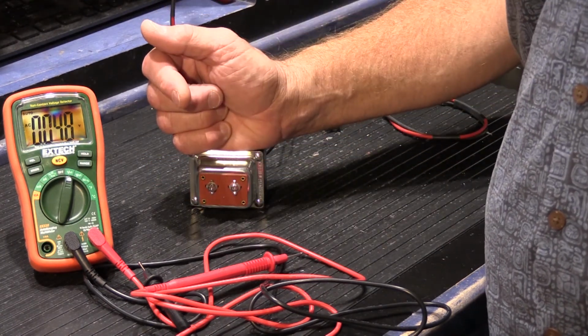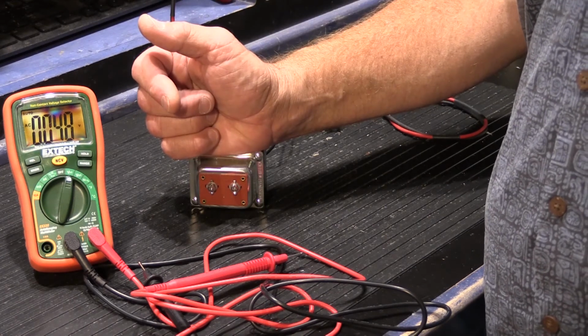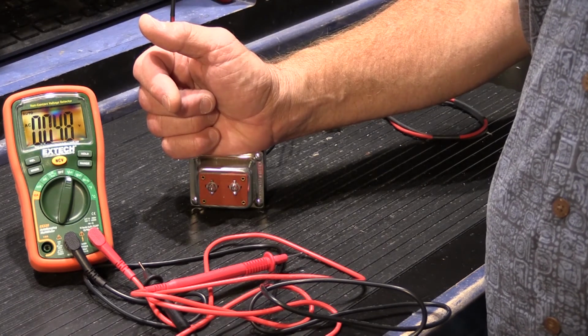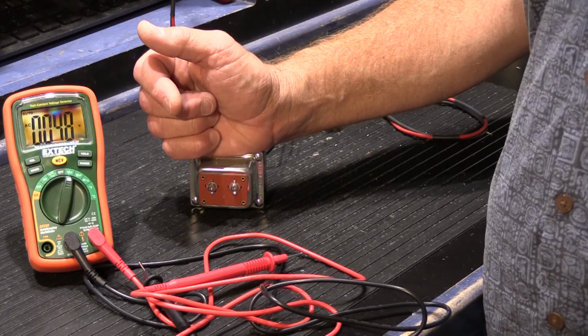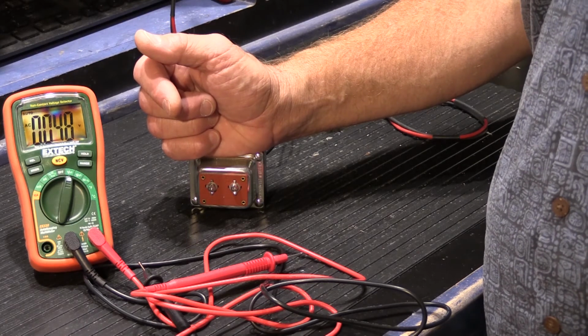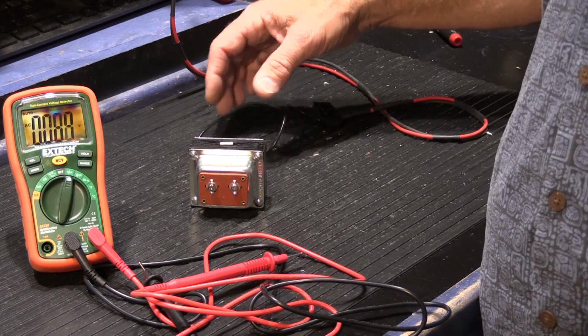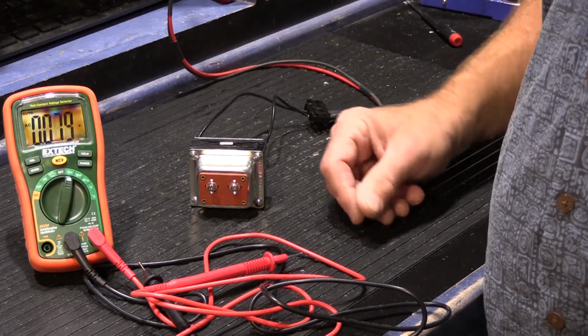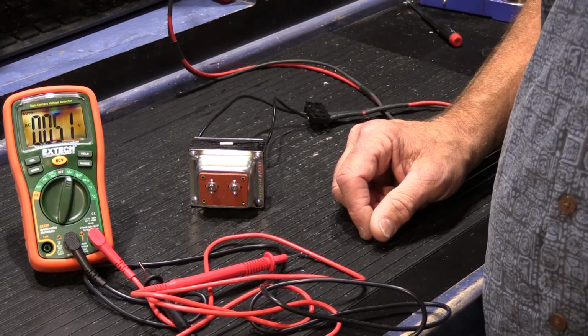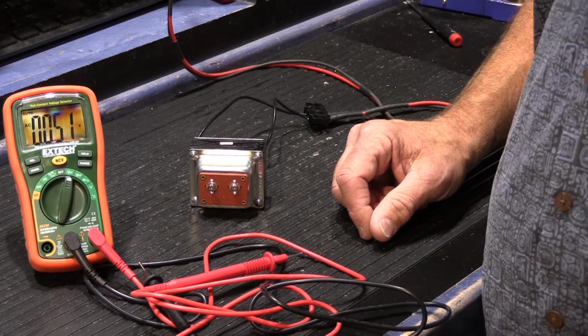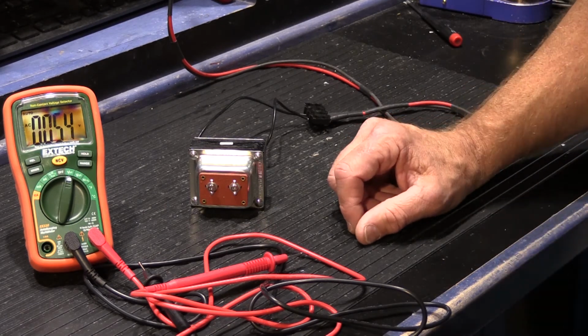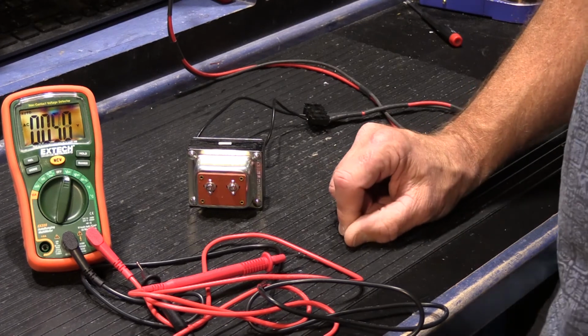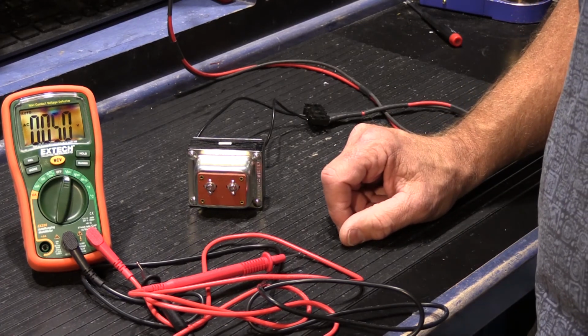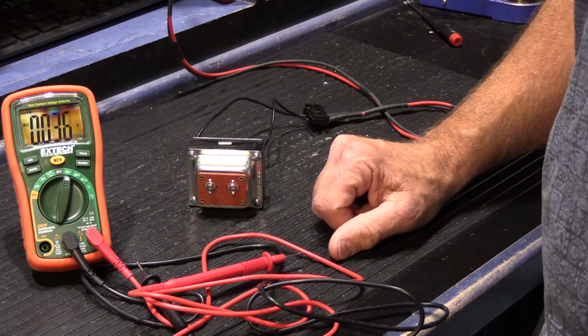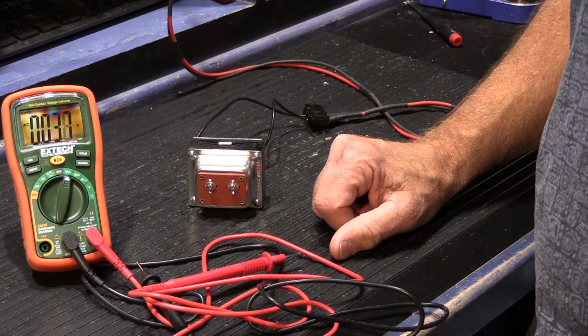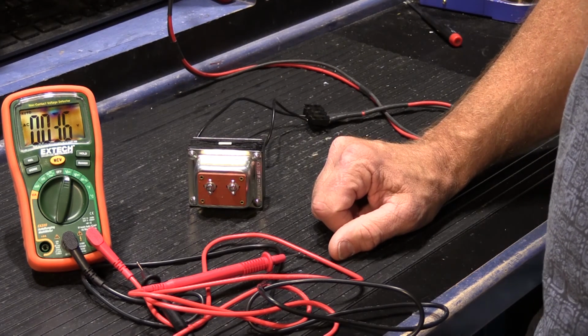It will become heat soaked. And heat soaked transformers sometimes never cool off. Even when you disconnect the device from them, they still will remain relatively hot. Even if you shut off the power on the primary side and let them cool down completely, when you turn the power back on, they will heat up again. I haven't seen that too often. In the 32 years I've been doing this, I have only seen maybe a handful, 5 heat-soaked transformers, so it's not very common, but it can happen sometimes.